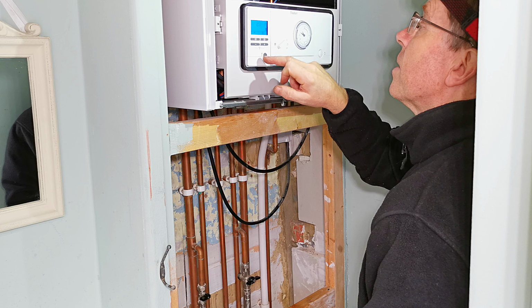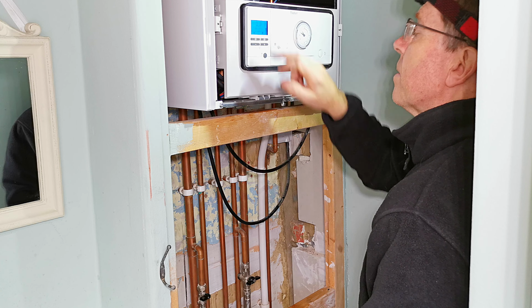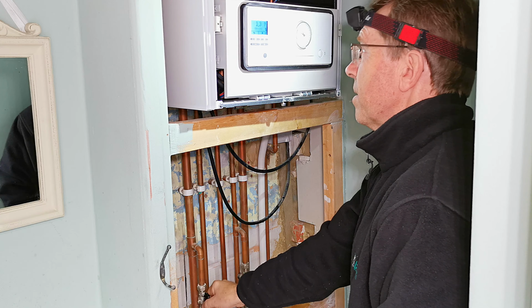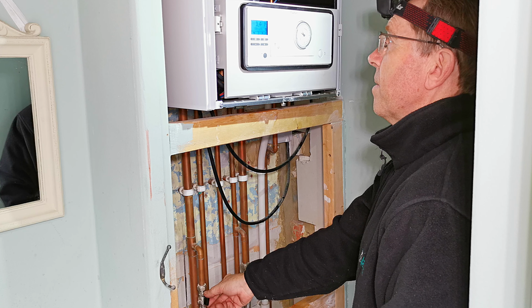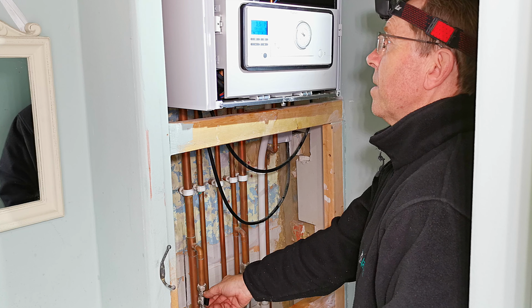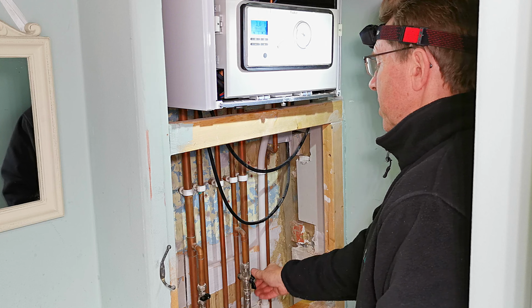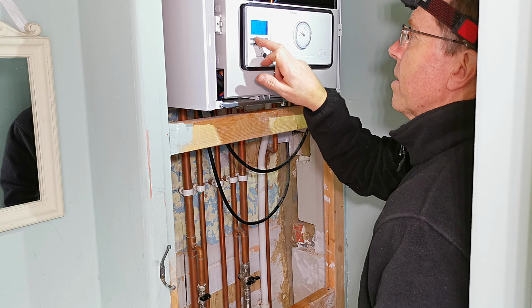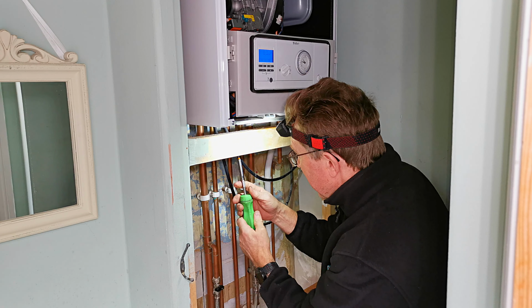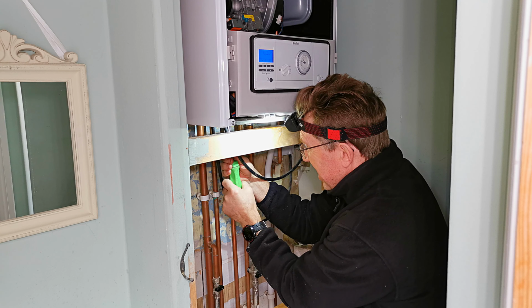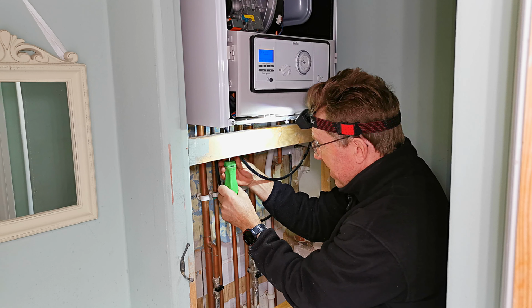I'm now just going to turn the hot water tap on and off a couple of times, reset the boiler a couple of times. That's going to keep the pump running and just circulate the water around the boiler and remove as much air from the boiler as possible. And keep topping it up until I've got about 1.5 bar of pressure in the boiler. Once I'm happy that I've got as much air out of the boiler as possible, I'm then going to open the flow valve on the central heating.